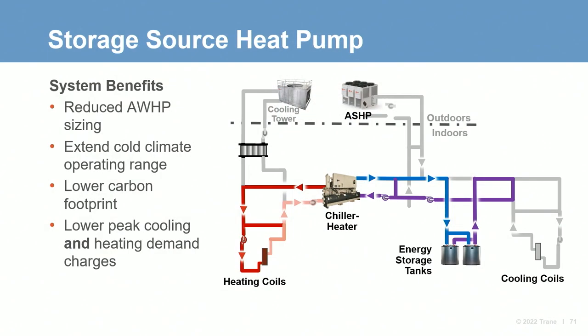This time-independent energy transfer can reduce air-to-water heat pump size by up to 50% and reduce the building carbon footprint. Energy storage tanks can also extend the electrified heating operating range in cold climates by enabling air-to-water heat pumps to only need to run during warmer hours of the day. And depending on the configuration and operating modes, the system can reduce both peak cooling and heating demand charges. Related system design strategies and tools will be discussed in a future E&L.